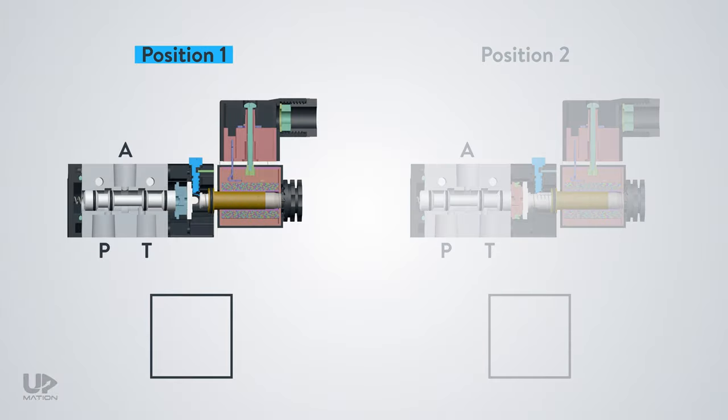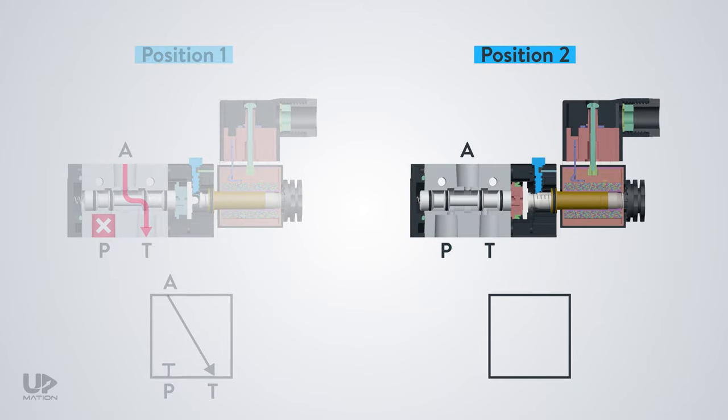In the first or the normal position of the spool, the fluid path is like this. Port P is blocked, and the service port A is connected to the tank port T. So, inside the relevant square, I'll draw a horizontal line in front of port P to show it is blocked, and an arrow from port A toward port T. In the second position of the spool, where the operator of the valve is actuated, the T port becomes closed, and port P becomes open, and as a result, the fluid flows toward the actuator. Inside the square, I'll put an arrow from port P toward port A. And this time, I put a block sign for port T.